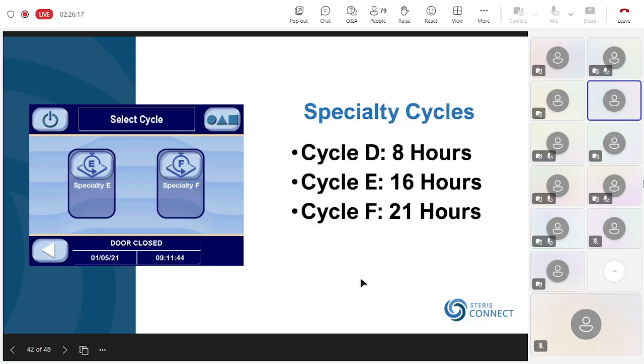And I know you're all going, why is this so long? The sterilant and the sterilisation cycle itself is very much like the sterilisation cycle we use for our vapor hydrogen peroxide machines. Whether that be a short cycle or a 50-minute cycle, it doesn't matter. The sterilant is the same type of process. Where the extra hours come from is aeration, where the vacuum is drawn and pulled out of the chamber so that we remove any residual vapor hydrogen peroxide from these porous devices.